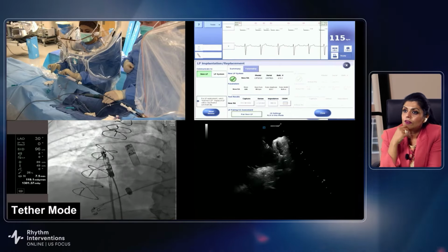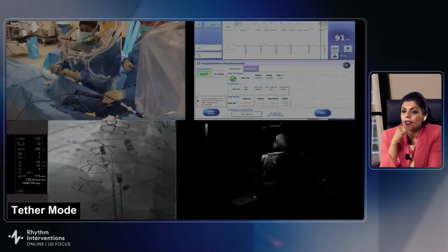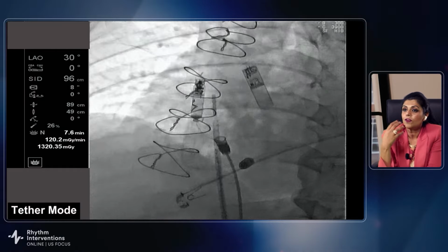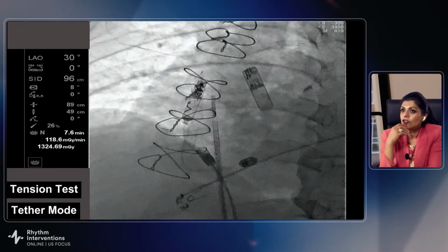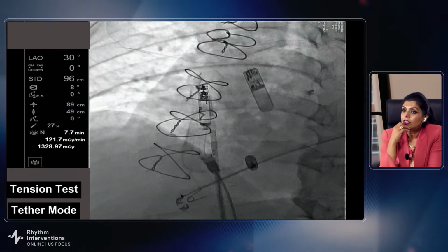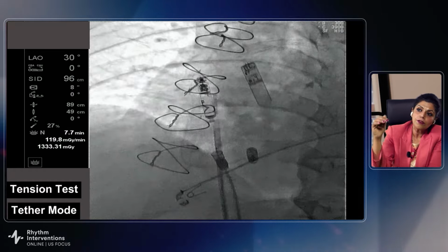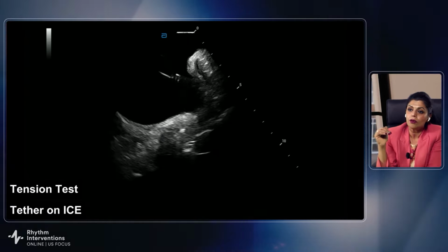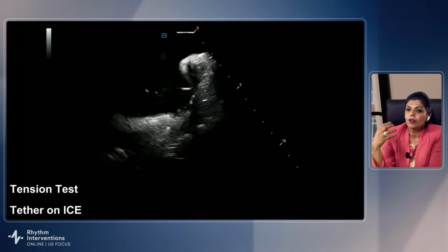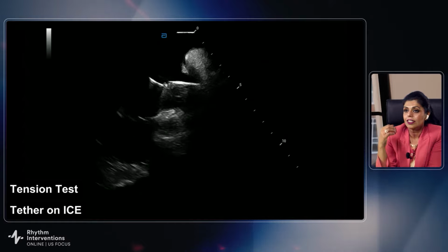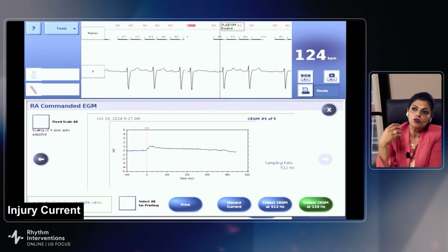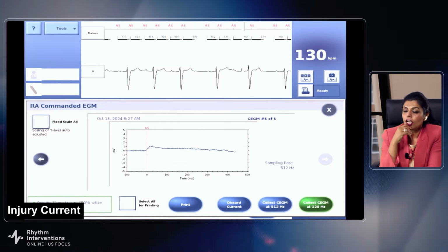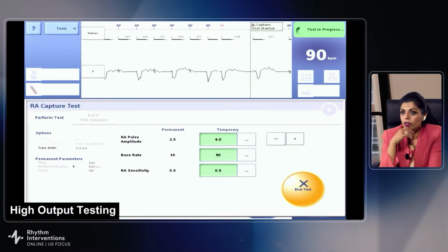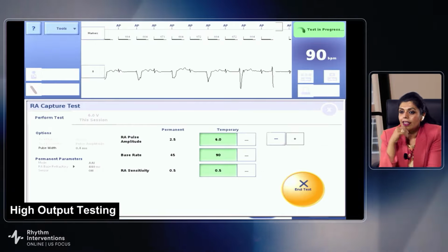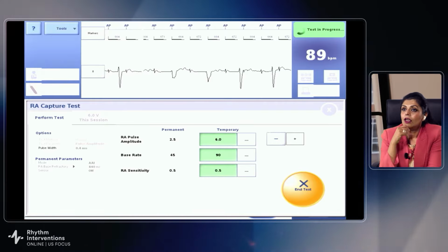Now with the AR2 device, we have started seeing a little bit higher impedance. And then once we have fixated, again 1.5 turns on that chevron, we come into this tether mode. For the atrial device, you'll see we're in this long tether mode, allowing for a better tension test and letting the device be in a more neutral position as we check the electrical parameters. So again, looking at that injury current and the impedance, we're testing here.